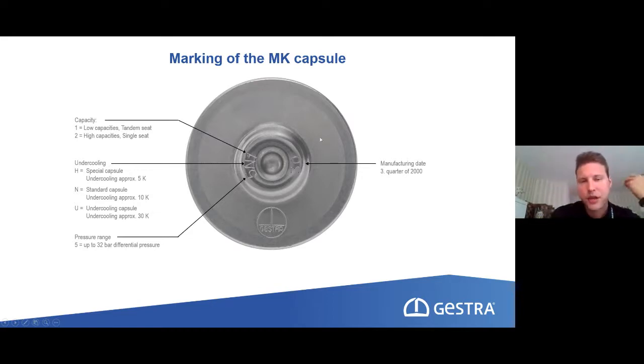How do we manage that? The liquid, the mixture, is a little bit different. It's a different kind of alcohol, and the amounts differ a little bit. So this is how we can manage that. Then the third letter that we see here is either a 1 or a 2. The 1 stands for low capacities, and it has the tandem seat with the additional plug we just saw on the picture before. So with this plug, which will guarantee an increase of the lifetime, this design takes a little bit of the capacity of this membrane type steam trap. It's not much. If we speak about only the flat-seated version of an MK, we can discharge, let's say, 400 kilograms per hour. If we think about the tandem-seated version, we can discharge 350 kilograms per hour, roundabout.